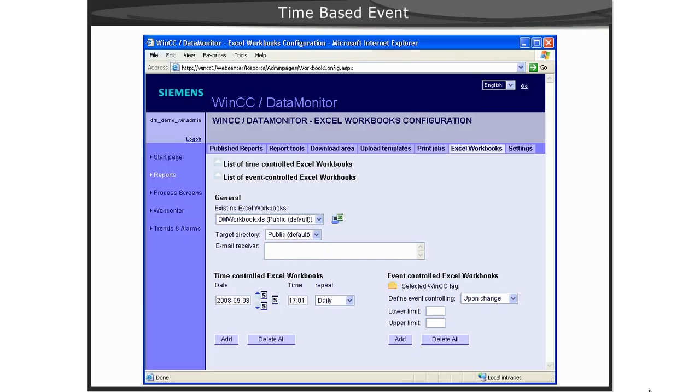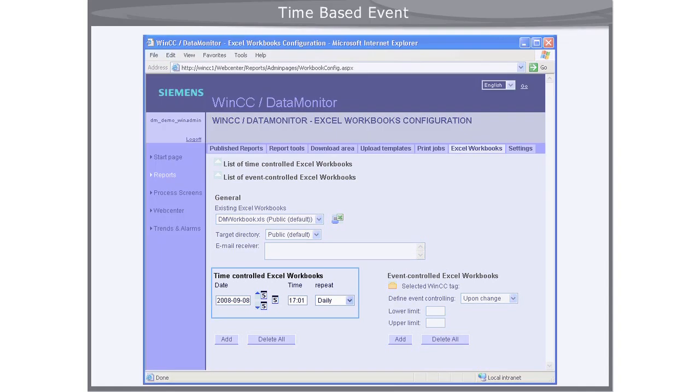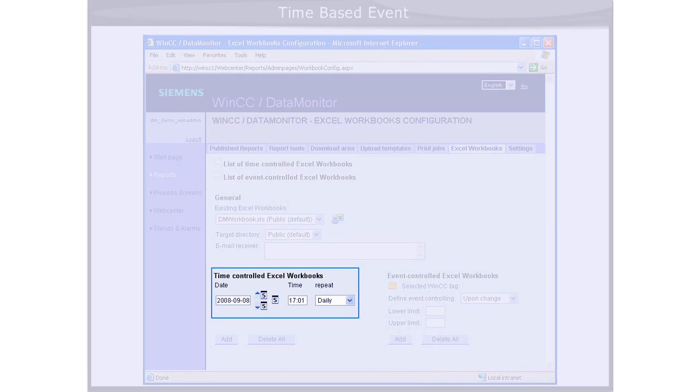A time-based event can be quite useful. For example, if you needed to create a shift report at the end of a production shift, you could use a trigger of a starting date with a time of, say, 5:01 PM, or 17:01, and then select a daily event for this.